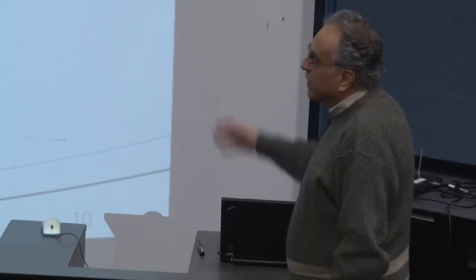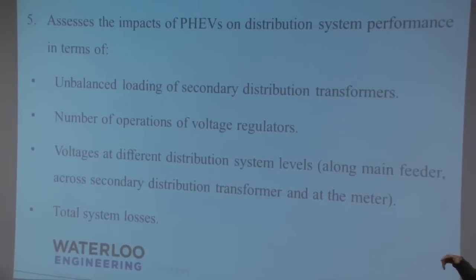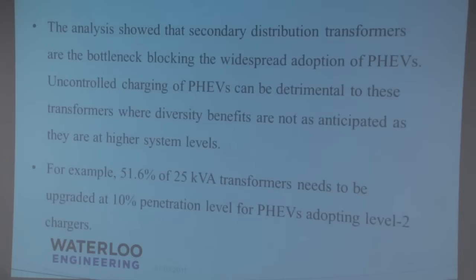We assessed the impact of PHEVs on distribution system performance. We looked at it in terms of unbalanced loading of the secondary distribution transformer, number of operations of voltage regulators, voltage at different distribution system levels along the main feeder, across the secondary distribution transformer and at the meters, and also at total system losses.